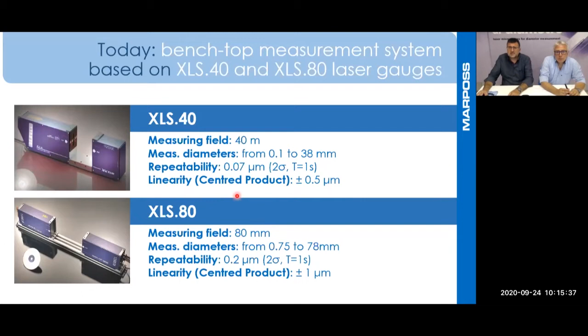The repeatability is very wonderful. The XLS40 with a measurement time of 1 second is better than 0.07 micron, so less than 1/10 of a micron. And for XLS80, the repeatability is 0.2 microns. The linearity with the product in the center of the measurement field has in this value also the error of the master that we use for the calibration of our instrument, that is 0.3 micron. The master that the certified laboratory gives us to make the calibration of our system is plus or minus 0.5 micron for the XLS40 and plus or minus 1 micron for the XLS80.